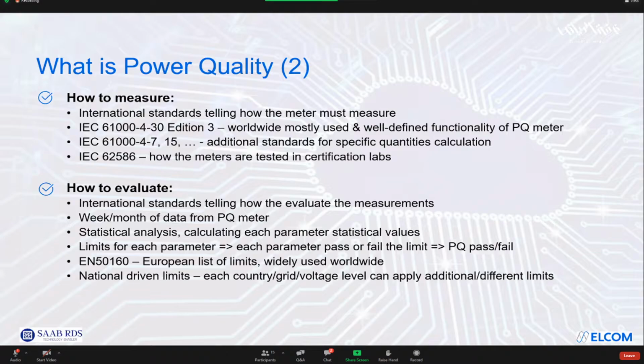So at the end, if you have a power quality meter from 2 or 3 vendors, the results should be the same. Here I'm mostly mentioning European standards, because from the power quality point of view, I believe we are much further ahead than the US or maybe China, because we have the best definition of these standards. In the US, I believe they are just looking at a few harmonics and that's it. But in Europe, we have to strictly follow power quality. So this is the definition of how the meter should measure. And then you have the meter, you measure some data, and then you should evaluate this data.